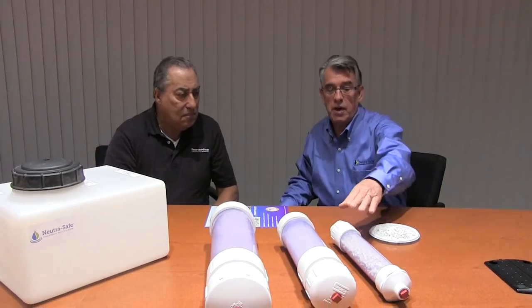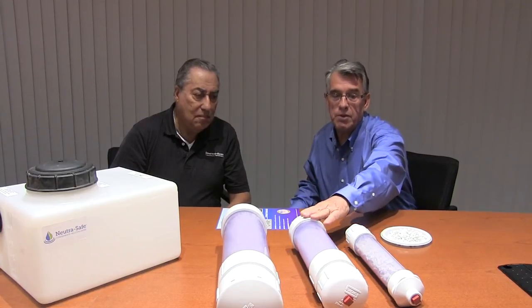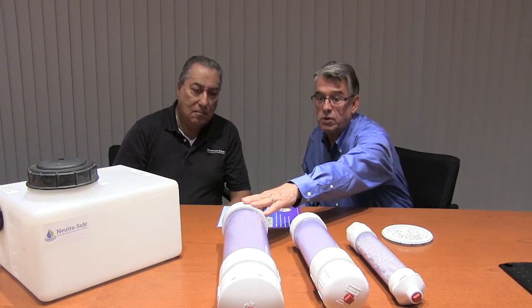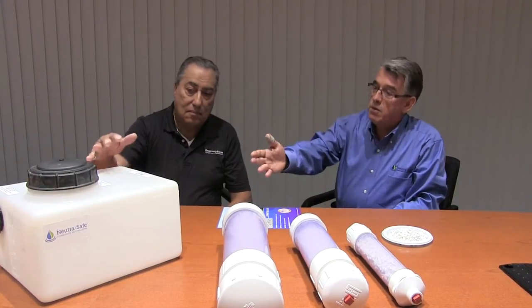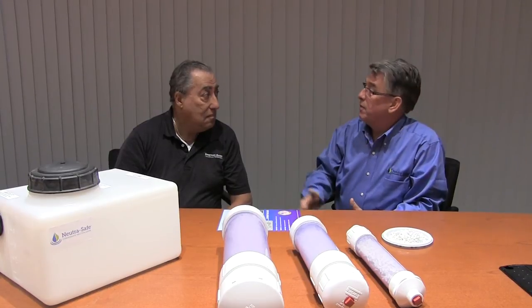Neutra-Safe has a complete range of sizing. We start out with our small 2-inch tube, which is rated for up to 220,000 BTUs in boiler input — that will cover most residential applications. Next, we have a 3-inch tube, which is good for 400,000 BTUs, covering some small commercial and large residential. Then we go up to a 4-inch tube, which is good for 1.2 million BTUs — at that point you're into commercial applications. We also have two tank sizes: a 5-gallon tank good for up to 6 million BTUs, and a 3-gallon tank good for up to 4 million BTUs.